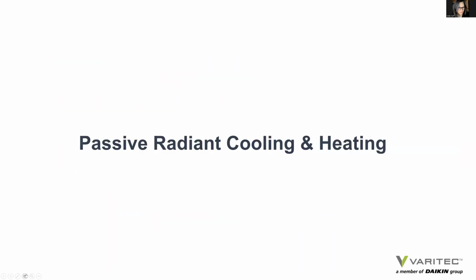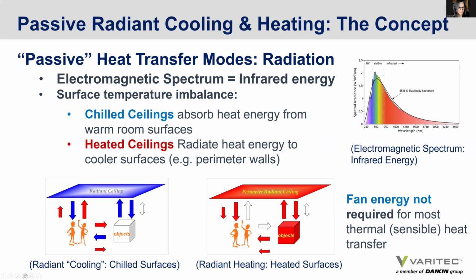Passive radiant cooling and heating is another passive heat transfer mode that can be applied in buildings. So passive heat transfer actually uses the electromagnetic spectrum as the heat transfer medium. By creating a thermal imbalance of surfaces locally within each zone, we can drive sensible heat loads in a space to a more dense heat transfer medium, such as water, and more efficiently remove that energy using pump horsepower versus fan horsepower that would otherwise be required. That can be achieved by cooling ceilings using chilled water temperatures of 3 to 4 degrees above space dew point, or heating ceilings to provide a radiant heat effect.